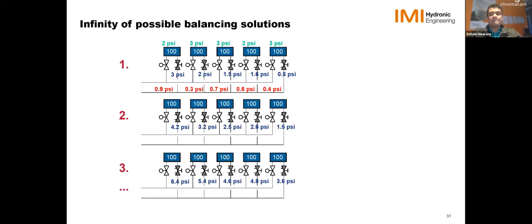And as I mentioned, balancing is important, of course, but we want to make sure we have the right amount of pressure drop for balancing. That's the ASHRAE rule I mentioned, with 1 foot of pressure drop or 0.5 psi. That's what we want on our index circuit, and that will define what pressure drop you're going to have in everything upstream. If we have a higher pressure drop on the index, you'll need a much higher pressure drop on your circuits upstream too.